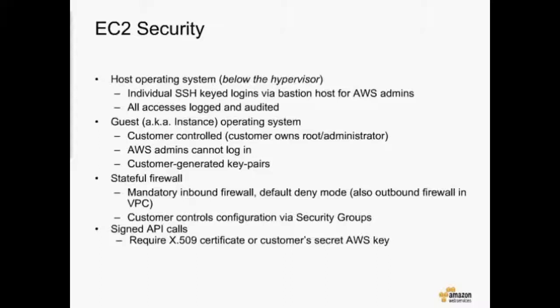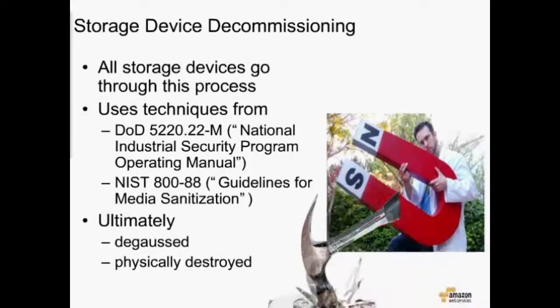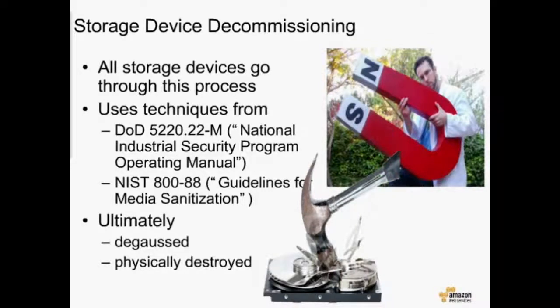One question we get quite a bit is what happens with storage decommissioning — making sure there are no data remnants on any of our hard drives. We have a very thorough process to decommission any storage media in our data centers. We start by doing a NIST-validated overwrite if the drive is still operating, then degauss it and physically shred the device as well. If it's an SSD-based device, we just do a shredding because degaussing isn't really effective for SSDs.